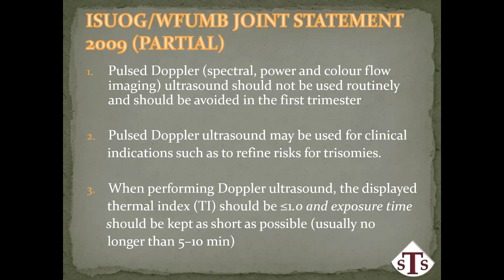So when performing Doppler ultrasound, the displayed TI should be less than 1 and the exposure time as short as possible and no longer than 5 to 10 minutes. This is logical, but unfortunately, because people have thought that ultrasound was so safe for so long, in a lot of cases, particularly with obstetrics, it has become treated like a toy. It is not. It is a serious medical modality with a risk to benefit ratio. And so it should never be performed if there is not a valid medical reason for it.